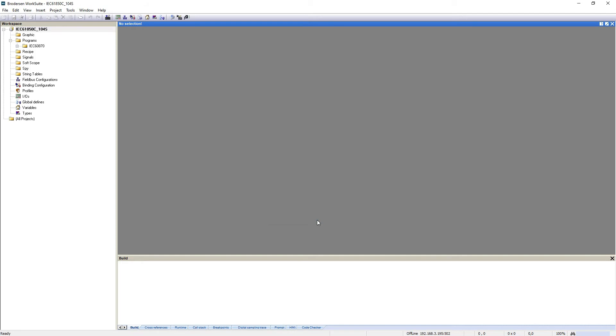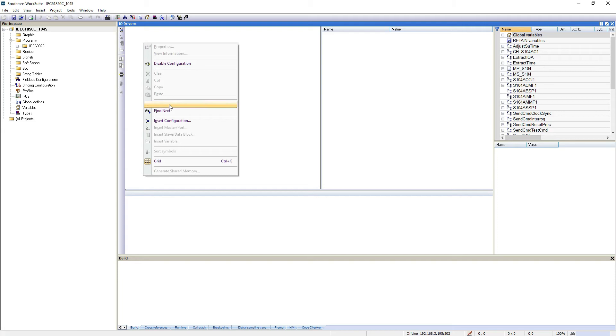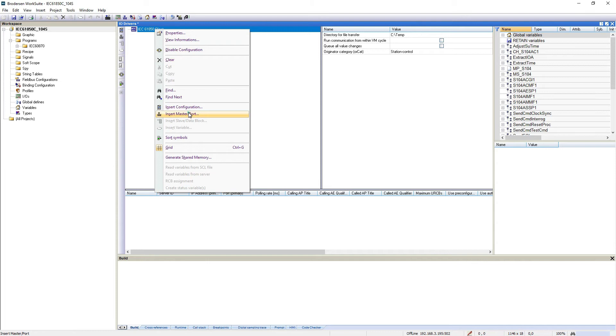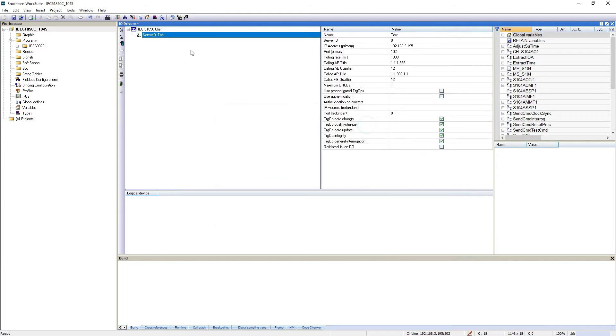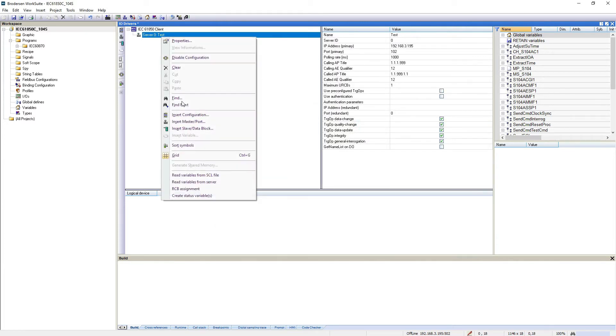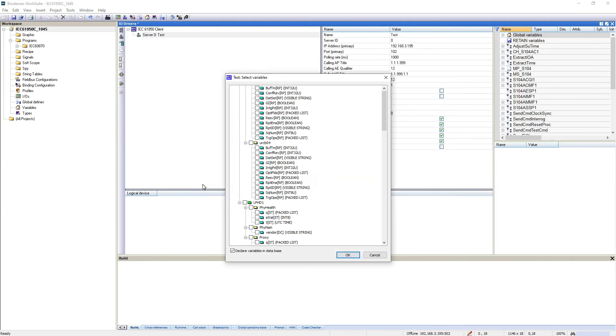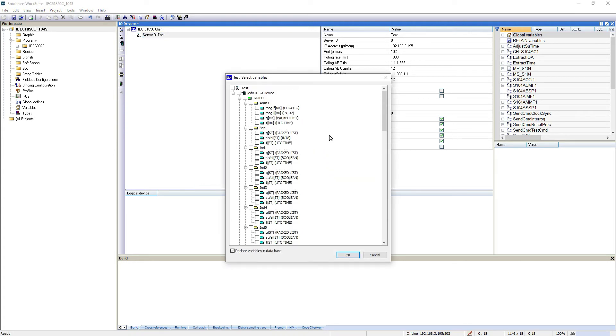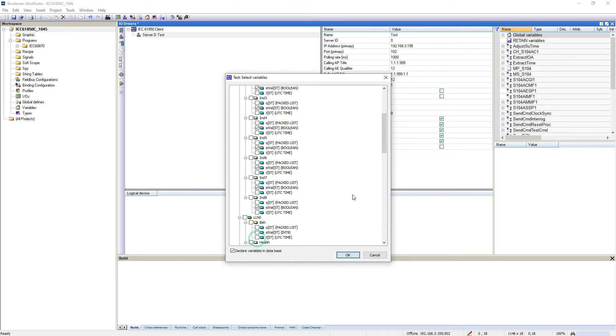What I need to do now is to add the configuration for the IEC61850 client so it can retrieve those data. I'll just add a port, call it test, insert the IP address of the IEC61850 server. Then I'll just query the server to get the data points available and I'll just select the right one. So this is my analog input, my digital inputs - eight of those.